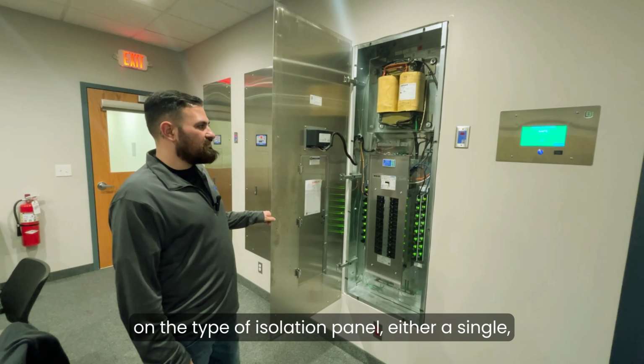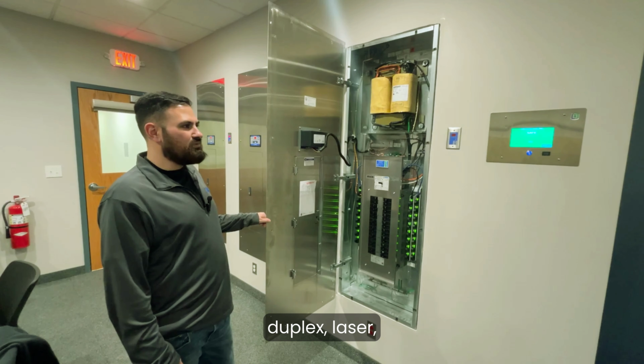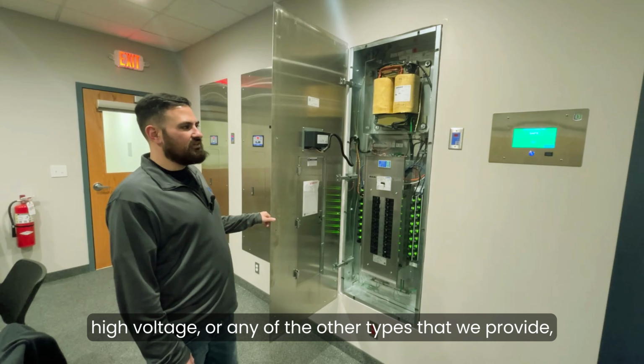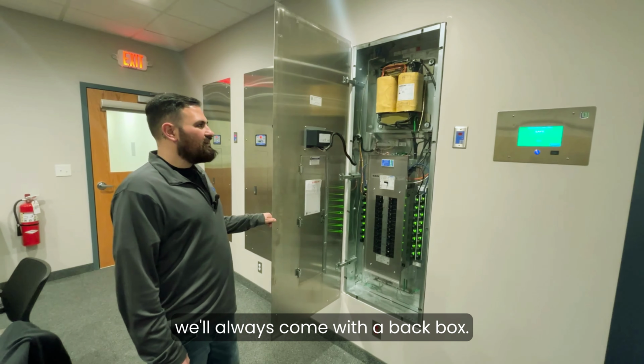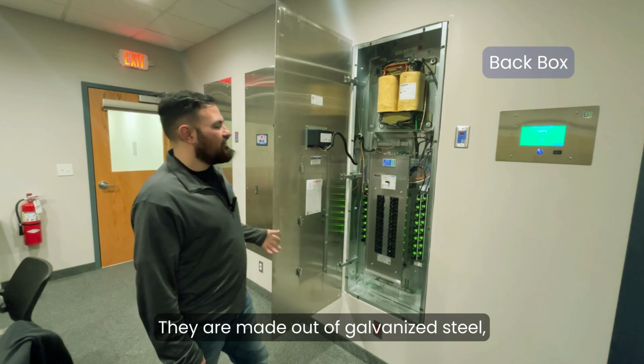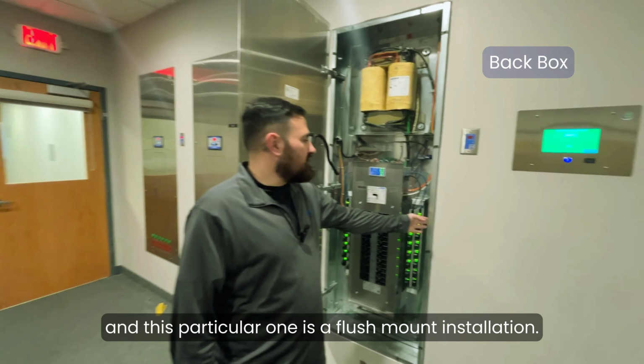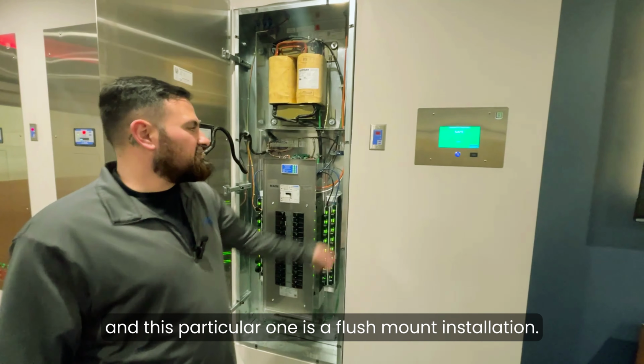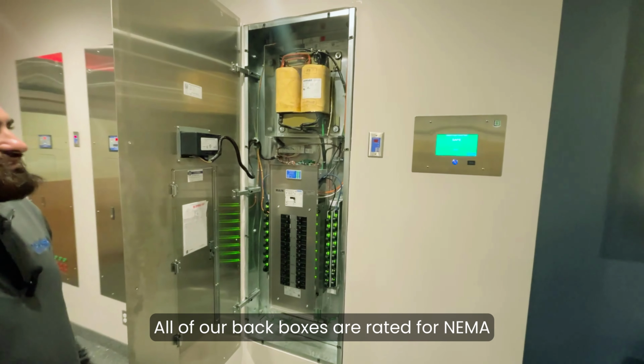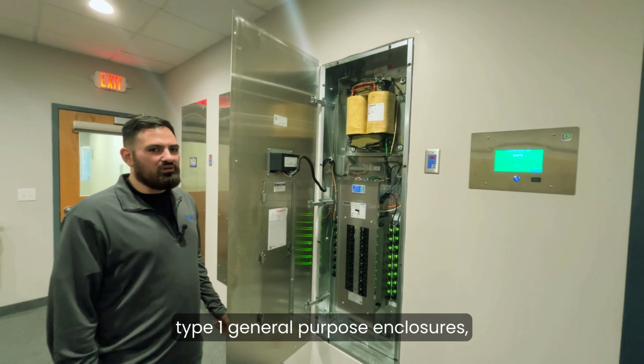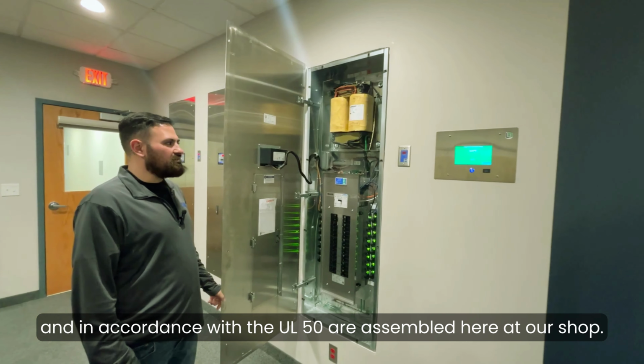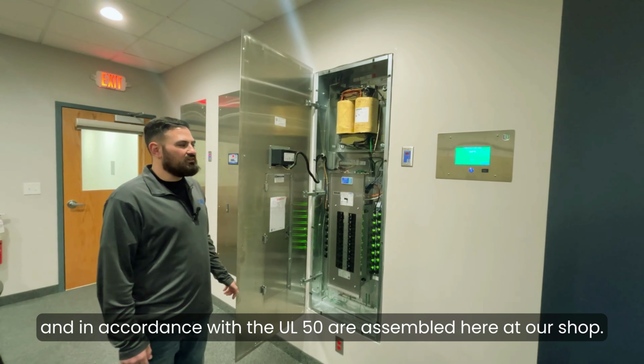Depending on the type of isolation panel - either single, duplex, laser, high voltage, or any of the other types we provide - it will always come with a back box. They are made out of galvanized steel, and this particular one is a flush mount installation. All of our back boxes are rated for NEMA Type 1 general purpose enclosures, and in accordance with UL 50, are assembled here at our shop.